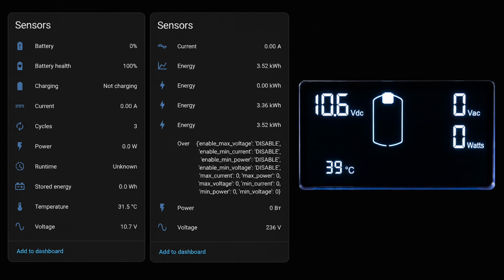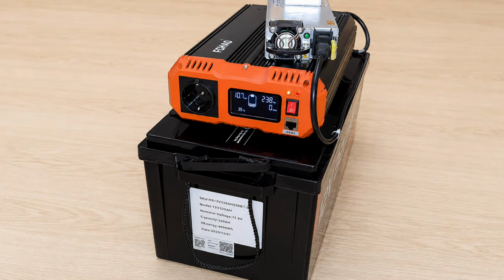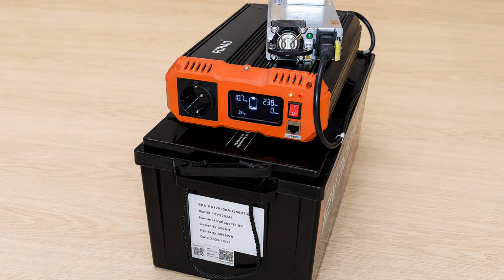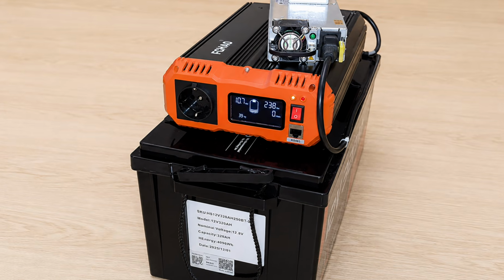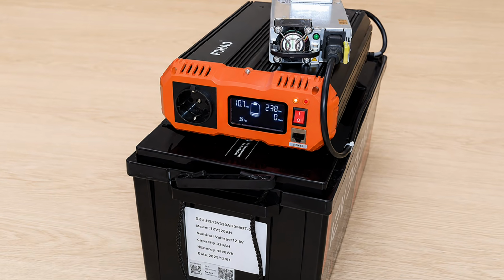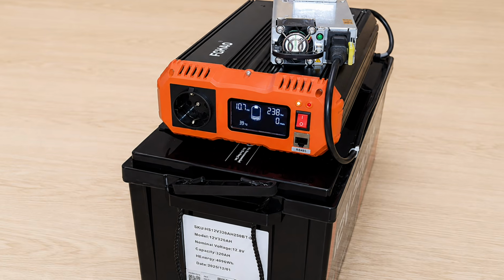Without a connected load, there is no sag, and the voltage values on the inverter and the BMS are almost equal. The battery was able to deliver 3,360 watt-hours of energy through the socket, which in terms of internal energy is just over 4,000 watt-hours, which practically matches the declared value. And that is considering that the discharge was carried out at a current above 120 amps. But once again, I want to emphasize that these 4 kilowatt-hours are the internal energy of the battery. When used together with the inverter, the conversion losses amounted to about 20% of the useful energy.